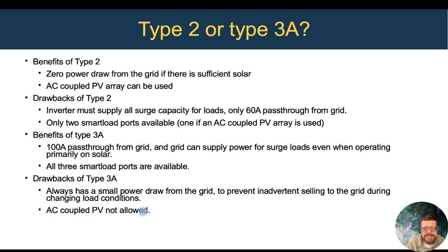There's also some differences in how the AC coupled PV is affected. Type 3A cannot do AC coupled PV. So if you want to do AC coupled PV, maybe taking an existing PV array that has microinverters on it already, then a Type 2 can handle that, but a Type 3A that's not allowed to export to the grid cannot do that.